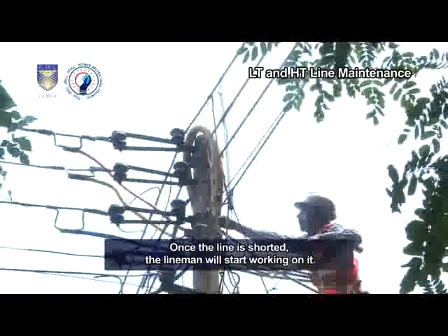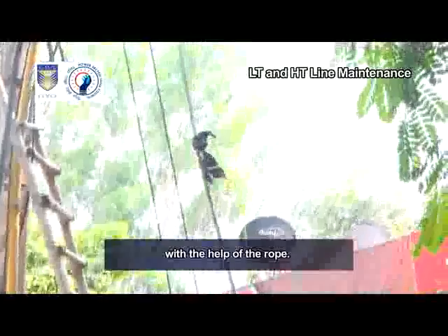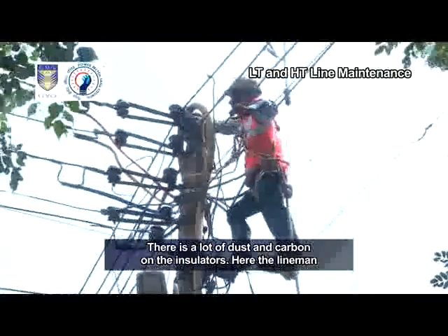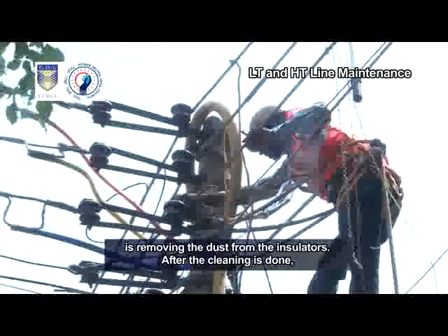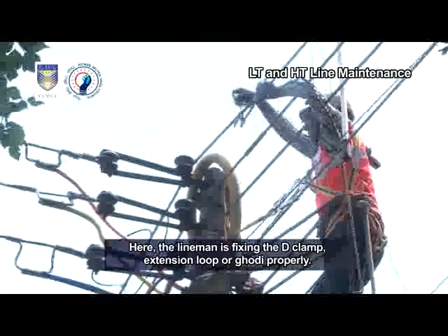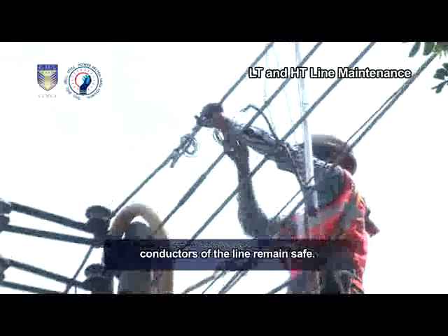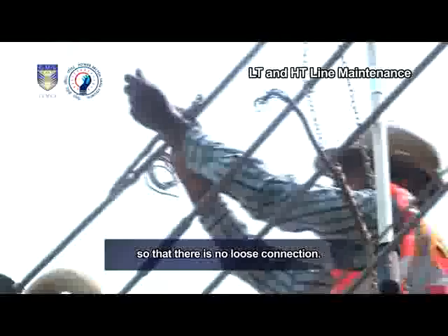Once the line is shorted, the lineman will start working on it. You can see that the helper is providing a D-clamp and a duster with the help of the rope. The duster is used for cleaning bushings and accessories fitted on the overhead line. There is a lot of dust and carbon on the insulators. The lineman is removing the dust from the insulators. After the cleaning is done, the lineman will start working on it. The lineman is fixing the D-clamp, extension loop or ghodi properly. He will then connect the service line with the D-clamp. If there is any carbon or fault in the lines, it affects the D-clamps and the main conductors of the line remain safe.